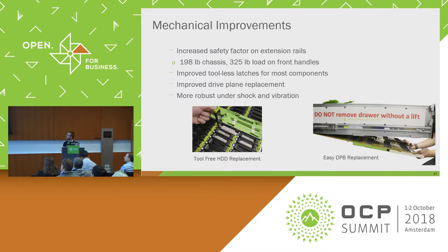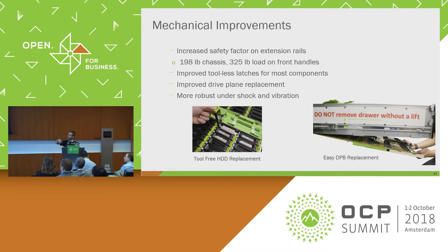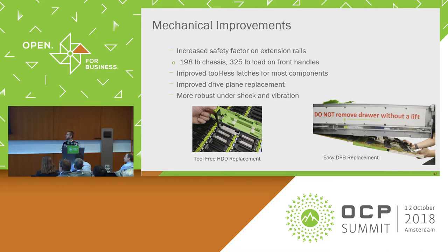We also improved the drive plane replacement process. The drive plane board is one of the biggest boards in the system with a lot of interconnections. Typically, replacing it required undoing lots of screws and removing all the components. What we were able to do is allow you to lift all the hard drives up — there's a spring support built into the hard drive latch that lets the drives sit up without fully removing them. Then you take out the compute card and SCC, and with the system fully pulled out, you undo four thumb screws at the bottom, slide the drive plane forward, drop it, and replace it all within about ten minutes.